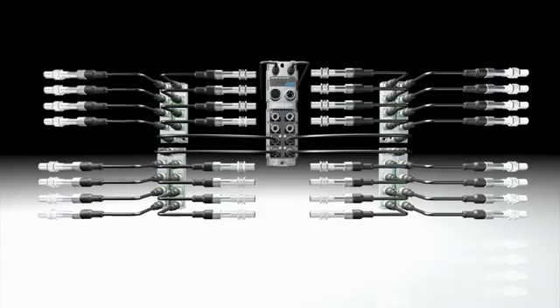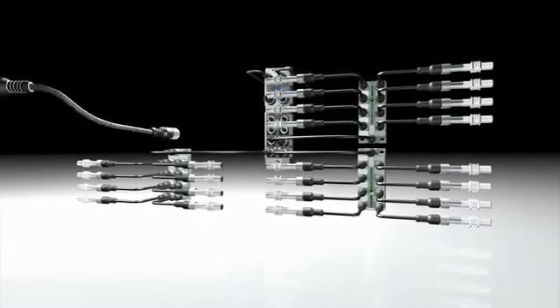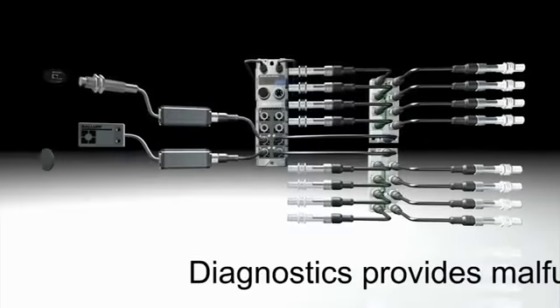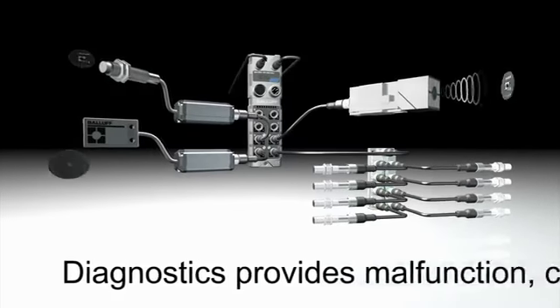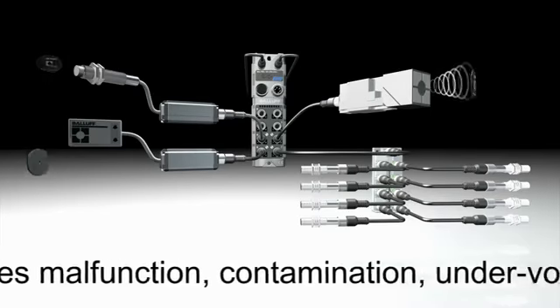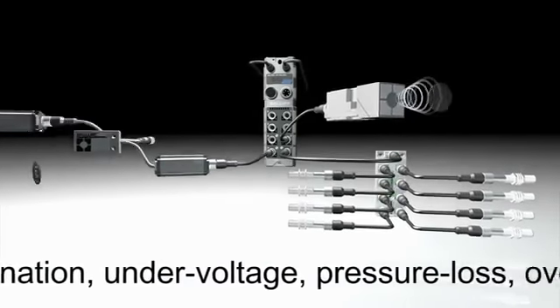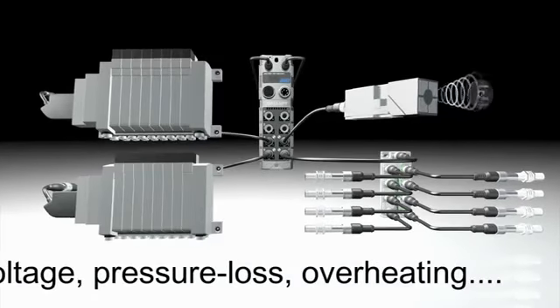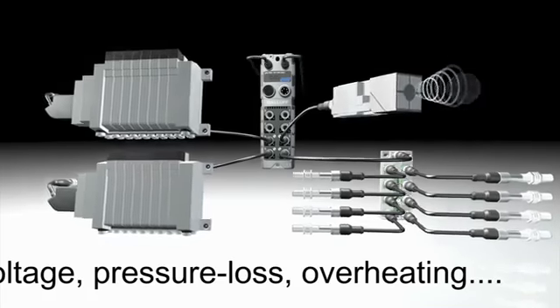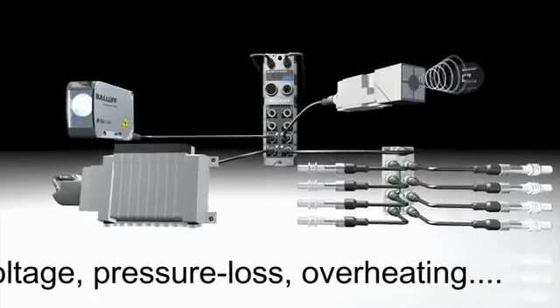IO-Link devices can provide information about the device status. Examples for diagnostic messages include malfunction of the device, contamination, undervoltage, pressure loss, overheating, time exceeded, etc. Cable break, loss of communication.